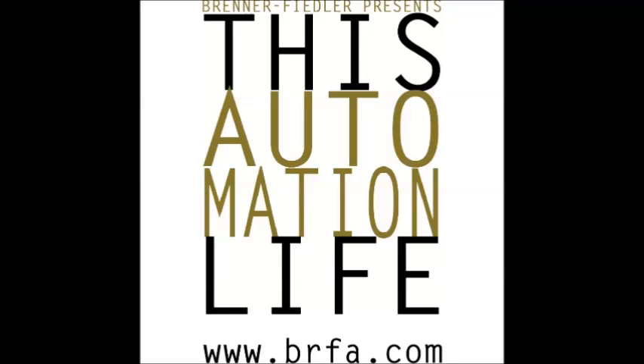Gotcha. So when I think about that, though, if you're using compressed air to generate vacuum, there must be some trade-off. Is it less efficient from an energy standpoint? It's definitely less efficient. It's about 4 to 1. So, in other words, if you had a requirement for a 1 horsepower vacuum pump, you would need a 4 horsepower compressor to drive that venturi. That's a big difference, realistically. And that's why, if you notice, the venturis are always much smaller flow. So that makes sense why it's localized to a very small point of use type of thing.